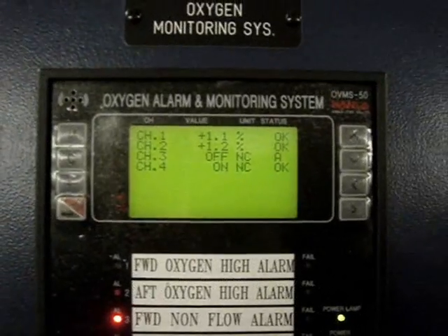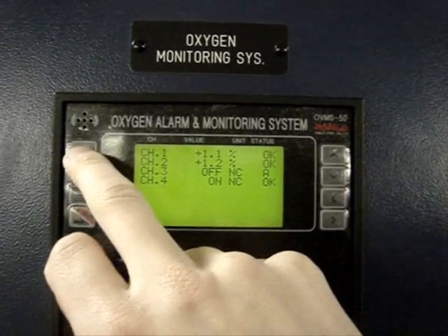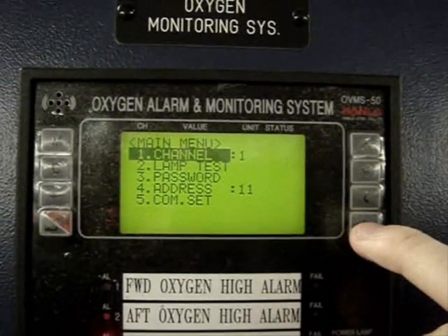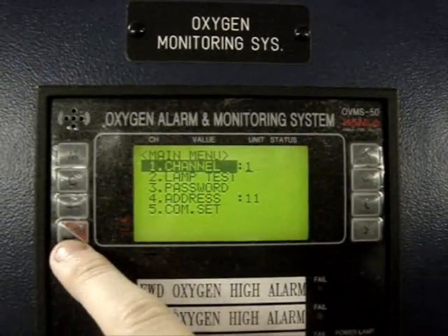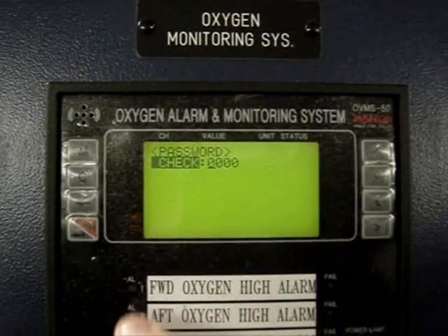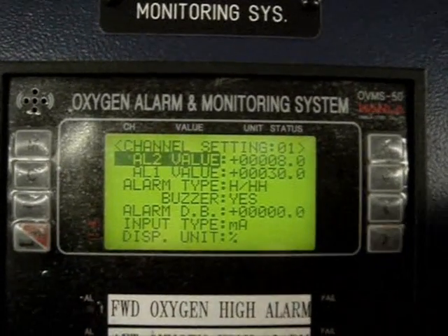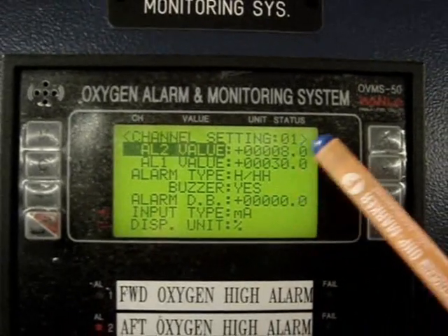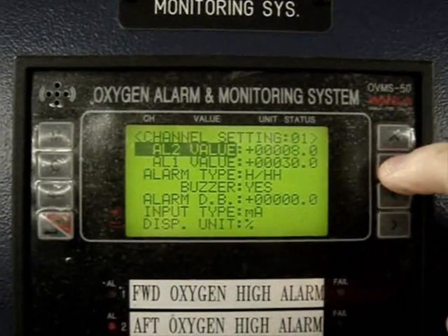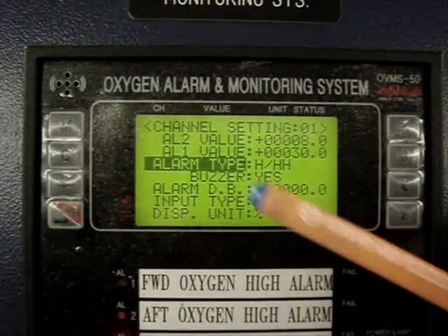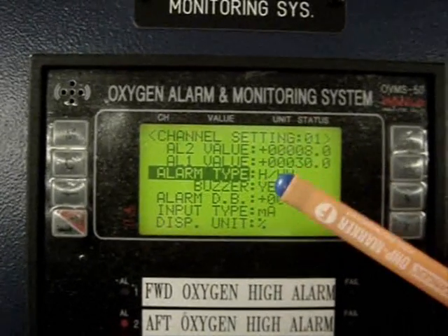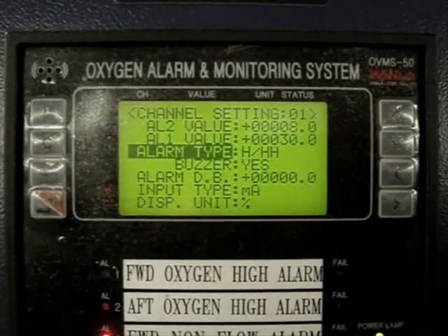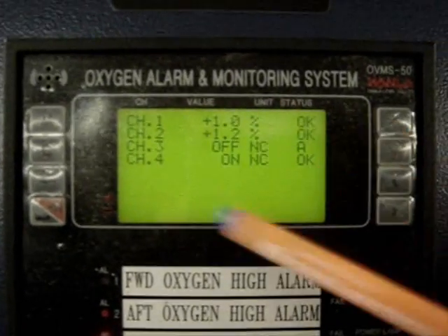To check the alarm set points, enter the menu by pushing the M button. Select channel one using the right button, then press the Enter button twice. The alarm set points are eight percent and thirty percent oxygen. H means high at eight percent and HH means high-high at thirty percent. If you don't push any button, the system will return to the normal display condition.